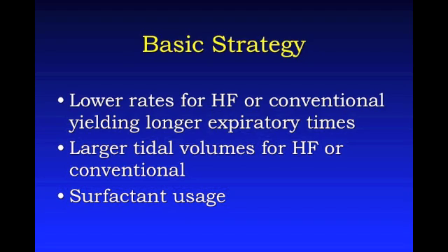Why do they use 10 to 15 hertz? Well, that's what we use on our preemies. That's what we use for everybody. As I've said when I give a talk on high frequency, I helped develop the oscillator, and if we didn't want the frequency changed, we wouldn't put a damn frequency knob on it. We would have just left it alone at one frequency. But we put a knob on it so you could change it, and you should be changing it.